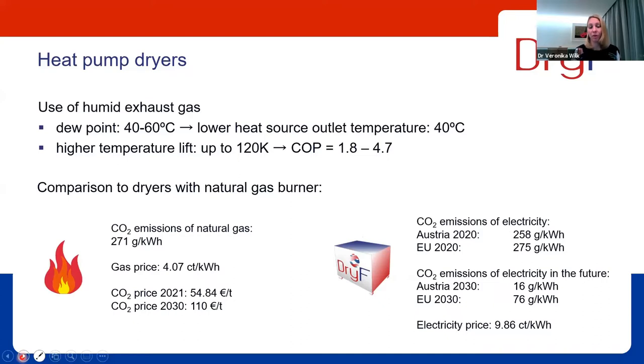If those heat sources are not available, still, a drying process is a very interesting application for a heat pump, and it has an interesting heat source in itself, and this is the humid exhaust gas. There we have all the water that is evaporated from the product that is dried within the process, and we can also make use of the condensation energy that is available there. But this comes at a price, because then we will lower the heat source outlet temperature of the heat pump. So we have seen that in the time series for the DryFiciency heat pump, we had values around 60 to 80 degrees C, and that will be lowered to roughly 40 degrees C when we use condensation and the energy that is present in the humid exhaust gas.